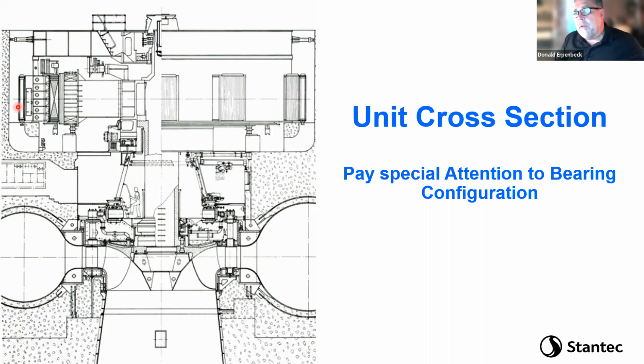This is the generator, but it's good to get a feel for this because I'm going to show you some different pictures. Pay special attention to the bearing configuration because this matters. We're not going to come back to this drawing that often. Up at the top, there is a guide bearing on the shaft just above the generator. It's on a big bracket and sits on the stationary stator. We'll see some pictures of this. The only way it's connected to the structure is through the foundation of the stationary part of the generator, and there are a couple of struts right up here that give it support to the wall on the left. Then this lower thrust bearing isn't connected to the concrete at all up here.